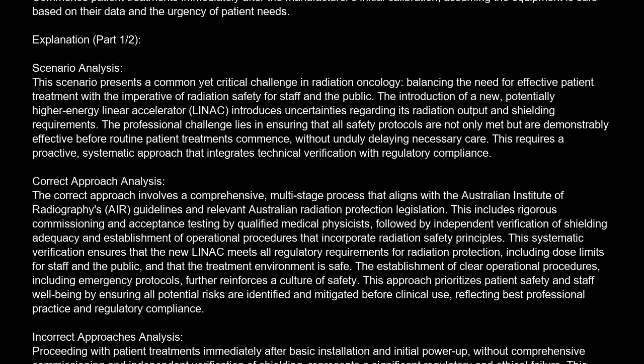Relying solely on the manufacturer's pre-installation calibration data without independent verification by a qualified medical physicist is also professionally unacceptable. While manufacturer data is a starting point, independent verification is crucial to confirm that the equipment performs as expected within the specific clinical environment and meets Australian regulatory standards. This failure to conduct independent checks breaches professional due diligence and regulatory requirements for equipment safety.